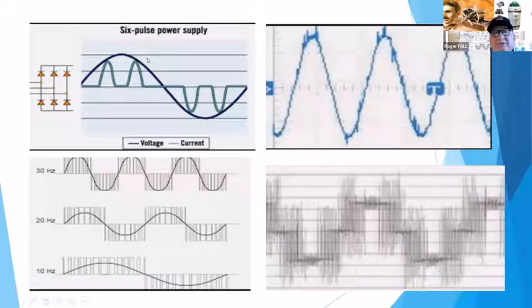So as you can see here, when the power comes in through that diode circuit that we talked about, the outer waveform is the voltage supplied from our source, the alternating current. This isn't actually showing a reading of what the input current looks like. Because these diodes are pulling power at different sequences, we get different ripples in here, and they call that harmonic noise. That is in different frequencies than the 60 cycle or the 50 cycle power supply we're providing. So this will be like 120 hertz current.